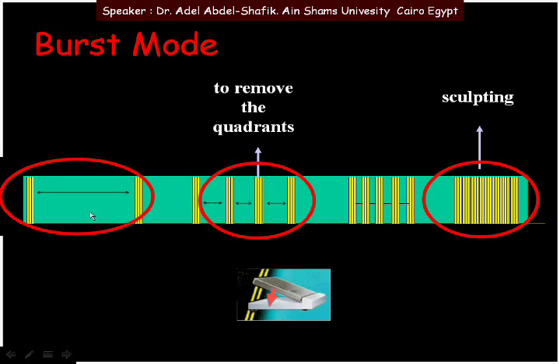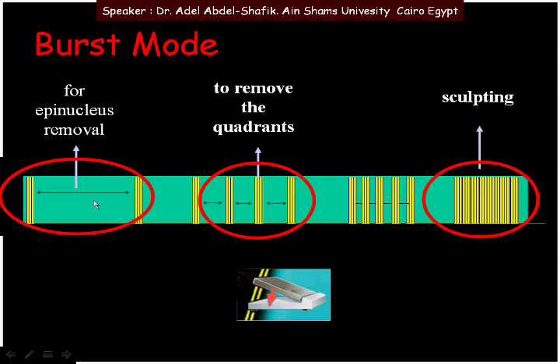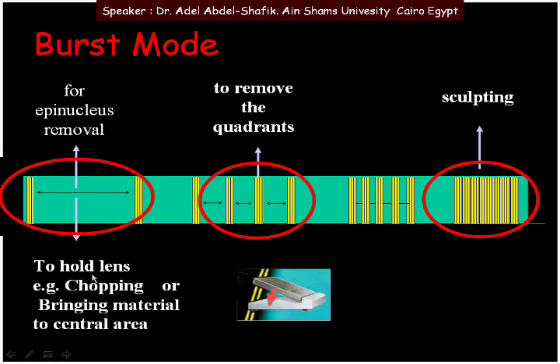With only a slight depression in position three, we have a very long off period, which is useful for removing the epinucleus using vacuum for mechanical removal, or for holding lens matter during chopping, or for bringing lens material back to the central area. By changing pedal position, we can make use of the ultrasound on and off periods as needed.